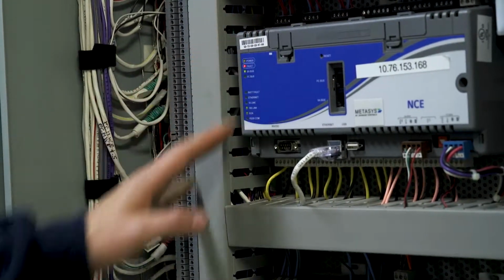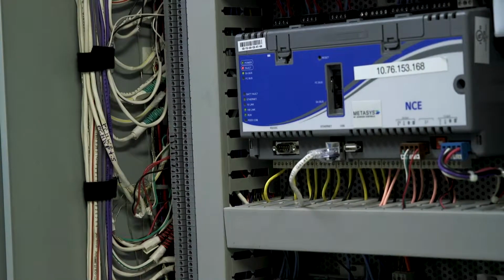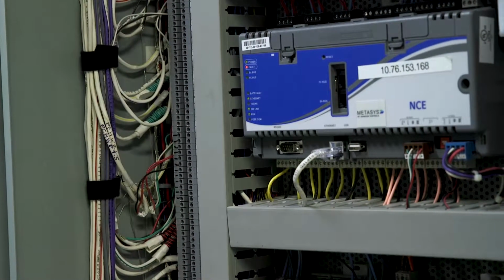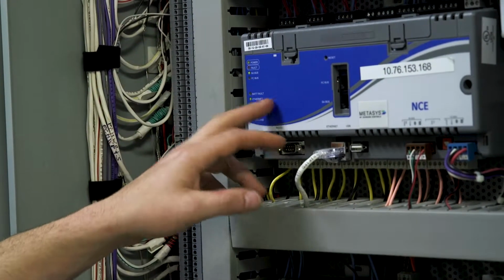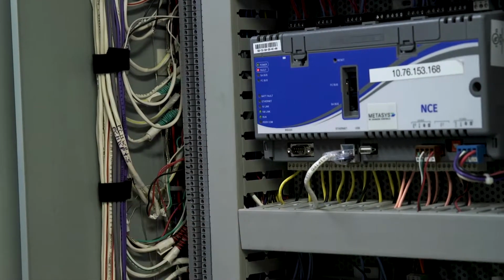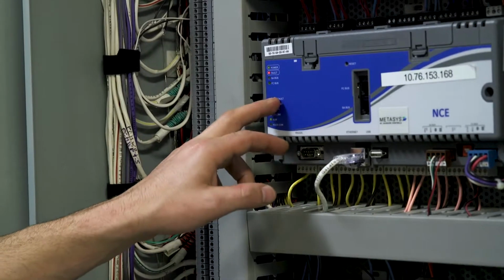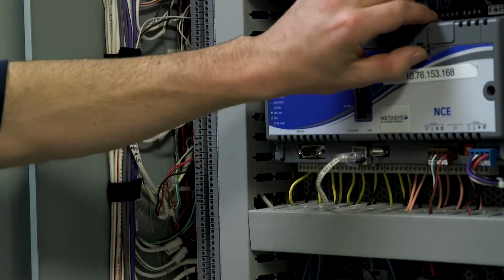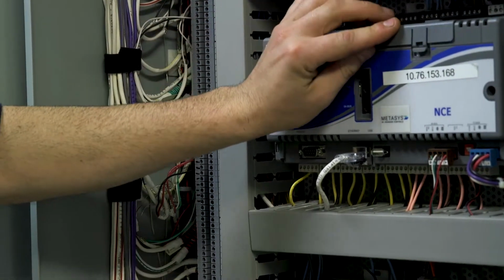Actually, that box itself, at the moment, it's not working, right? Yeah, if it's solid red, then it's not working at all. If you have an issue with the battery, on this one it'll tell you if there's a battery fault, and then your battery's under here. There's no battery in the other one. And they suggest every 3 years you replace the battery.